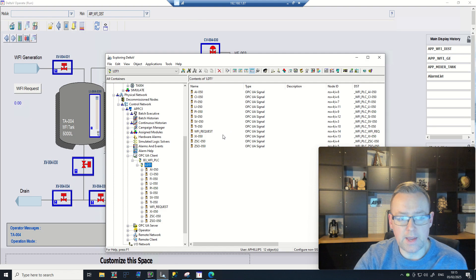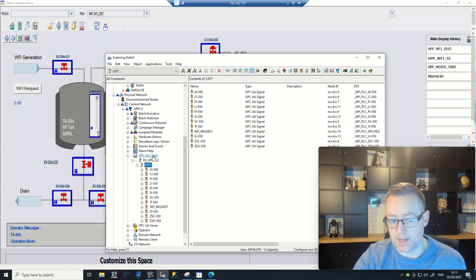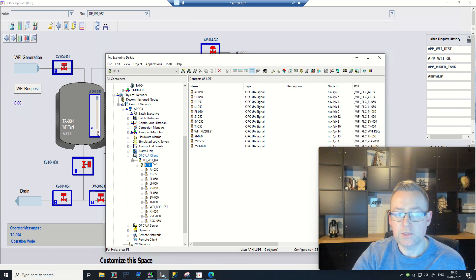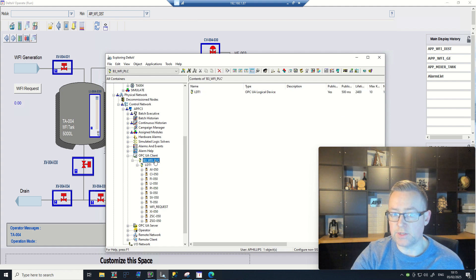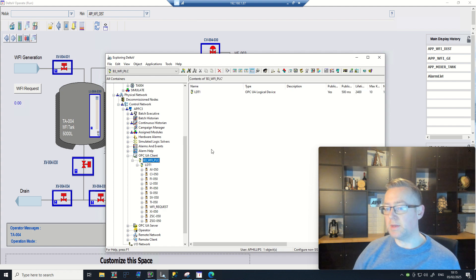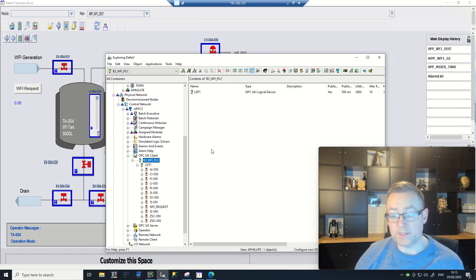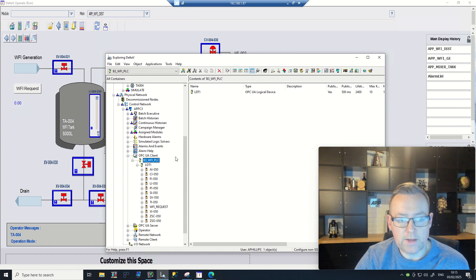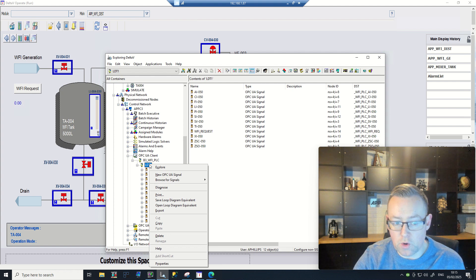Inside Delta V there is an area called OPC UA Server and then OPC UA Client. When you're inside the client, you can set up individual devices, which means you can browse for OPC UA servers. When you actually create the device, you can go off and browse the OPC UA server as it has been set up.